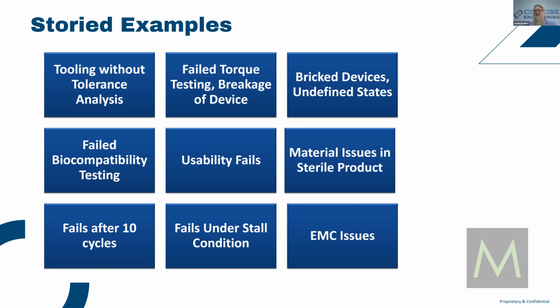On the material issues for sterile product, you can imagine if you make an error there, you find out that you're probably not going to pass biocompatibility, or maybe your device is starting to merge with the PETG or merge with the Tyvek, which can happen in shelf life. Those things set you back sometimes 9 months or a year. So you need to know that somebody's done this before, or you've seen it before, or pre-test some things to make sure that you don't have those issues. I think that's enough little stories.